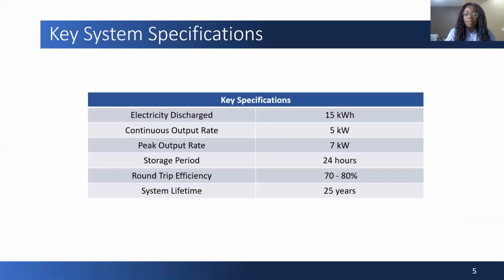The system must be capable of discharging 15 kilowatt hours of electricity with a continuous output rate of 5 kilowatts and a peak output rate of 7 kilowatts. This design will store heat energy for 24 hours, which means that after this storage period, the system should have enough energy to be able to produce the 15 kilowatt hours of electricity. The round-trip efficiency should be in the range of 70 to 80%.